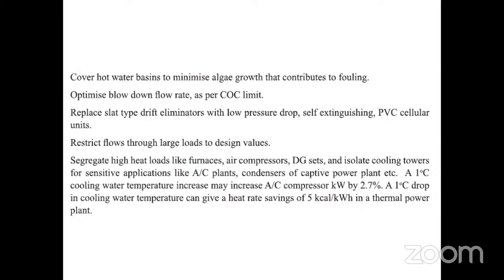Replace the drift eliminators with PVC cellular units. Restrict, and this point also I am not aware, sir. Just have it in mind. Otherwise, next time I will search for it and explain it. Restrict flows through large loads to design values. Segregate high heat loads like furnaces, air compressors, DG sets, and isolate towers. We have to keep within the rating of the cooling tower. That's all. I think we have come to the end.